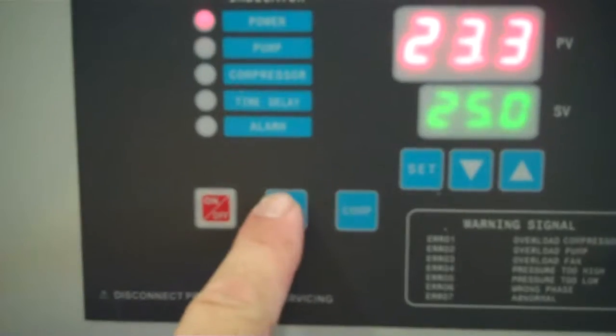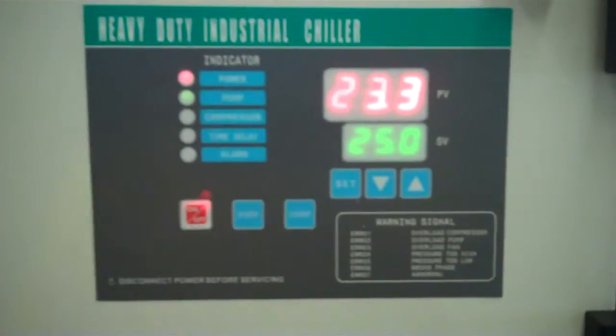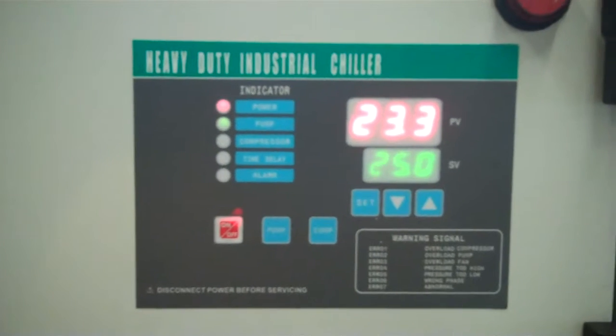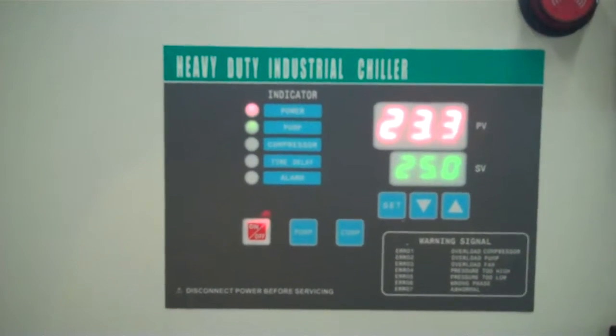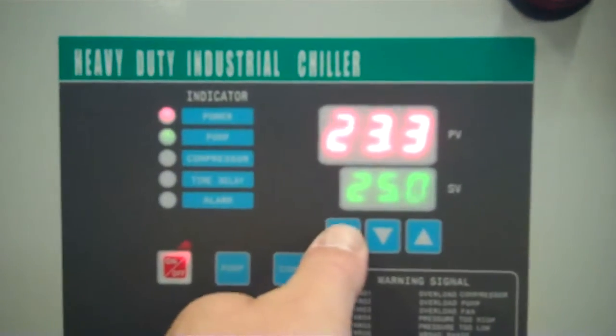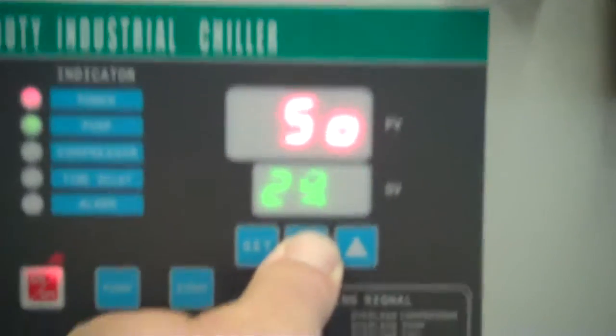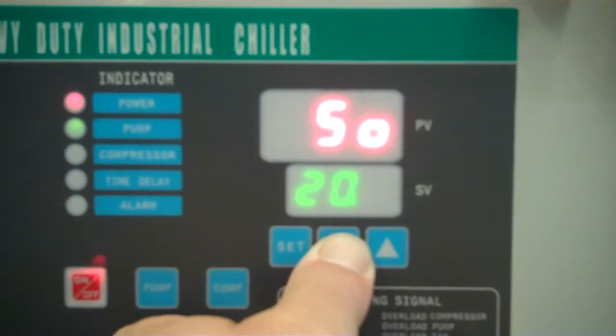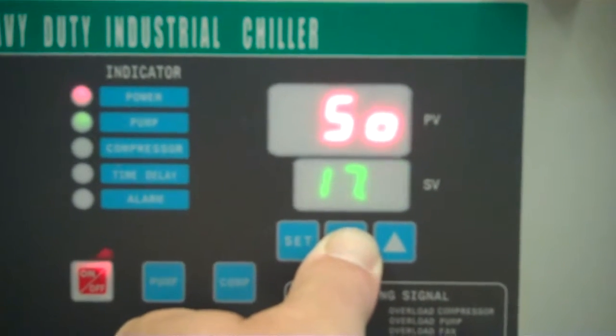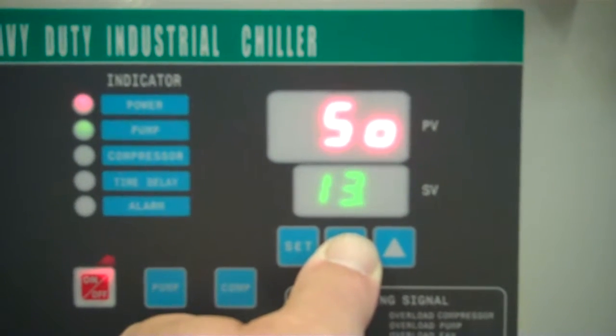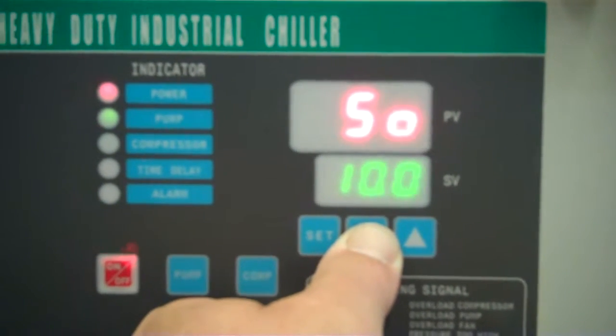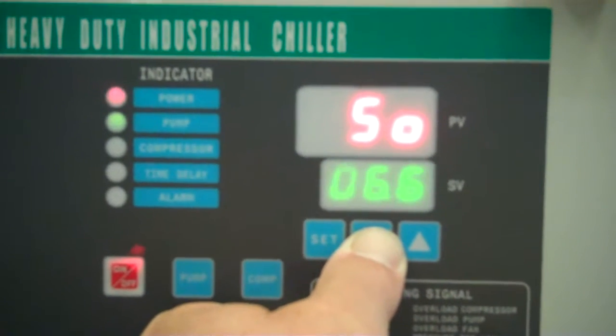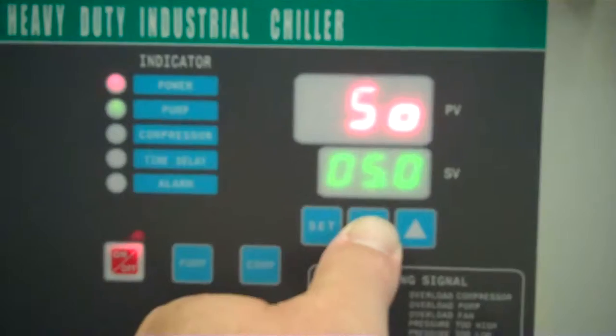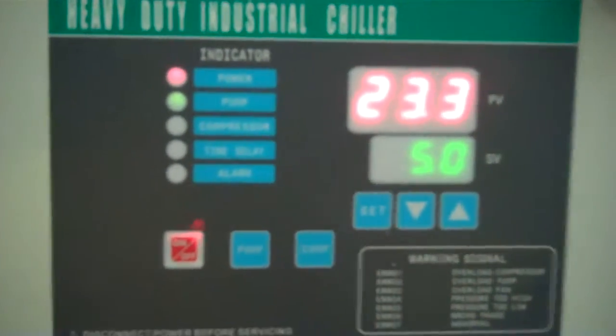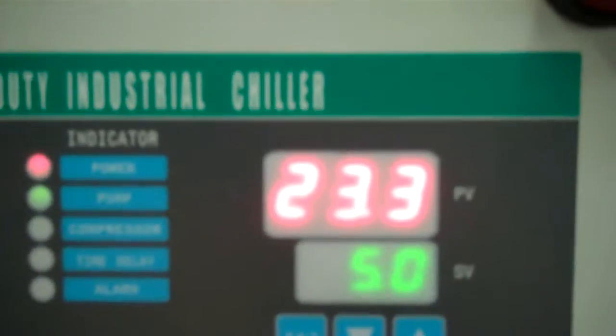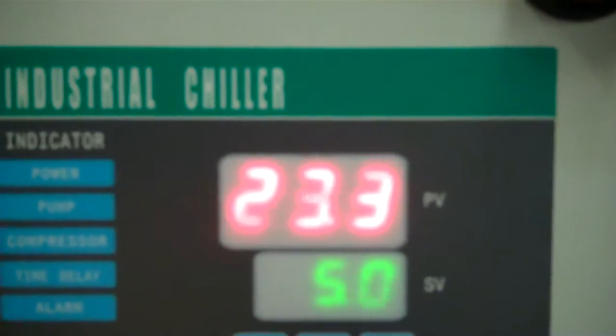First thing I'm going to do is turn on the pump and get some fluid, the glycol mix, the water mix flowing through the chiller. Next we're going to bring our set point down to the lowest part of the range. These have a set point from 5 degrees C to 25C, which is approximately 42 Fahrenheit up to 77 Fahrenheit, give or take. So I just press the set button, and bring it down to 5 degrees C, press set. The water in the tank and the piping is just under 25C right now.